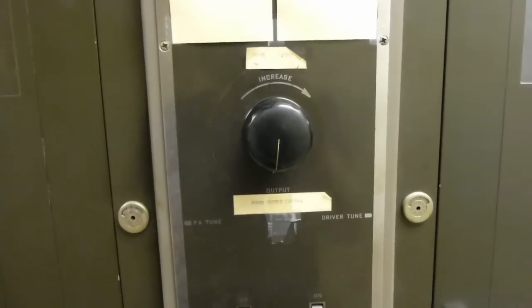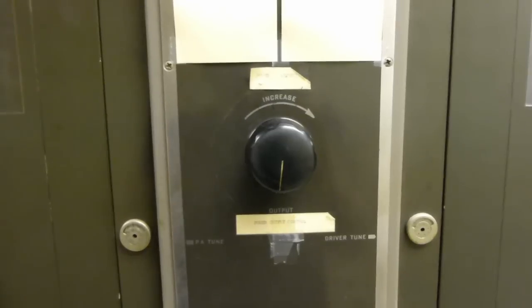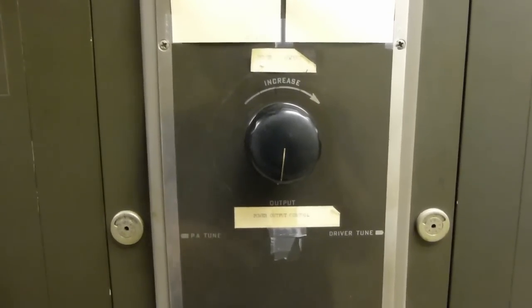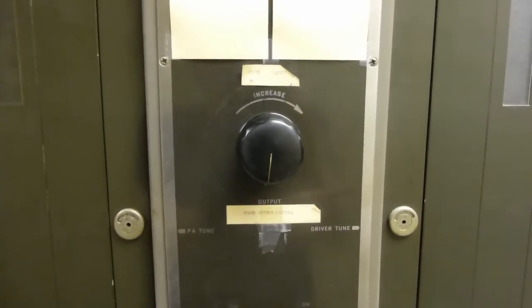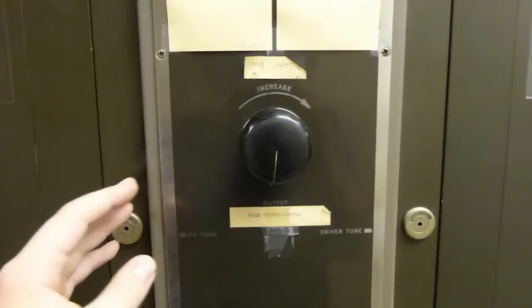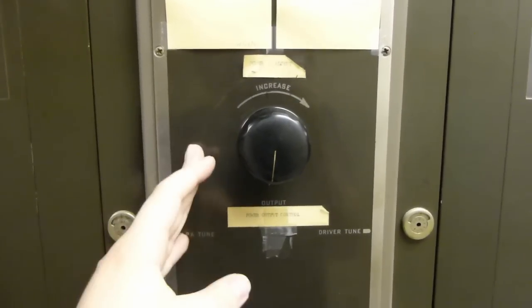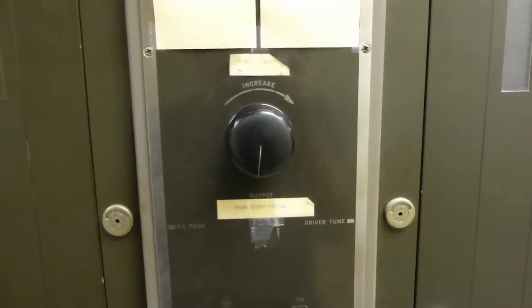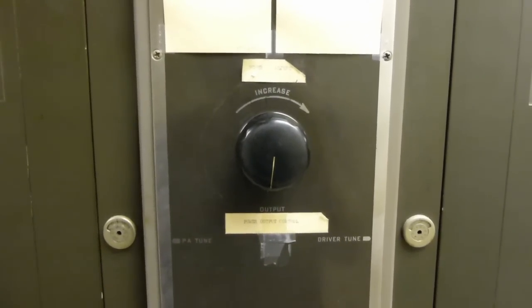The way this works is the other trick that RCA did with the thyratron tubes: there's actually a pulse generator in here that generates a pulse train intended to fire the thyratron tubes in cabinet four. This varies the phase relationship of those pulses to the incoming AC line. By shifting this, you can vary where the pulse hits and at what point on the AC waveform it starts conducting, so that you can vary the voltage up and down. If you think that sounds like how modern solid-state dimmers work, you would be absolutely right.